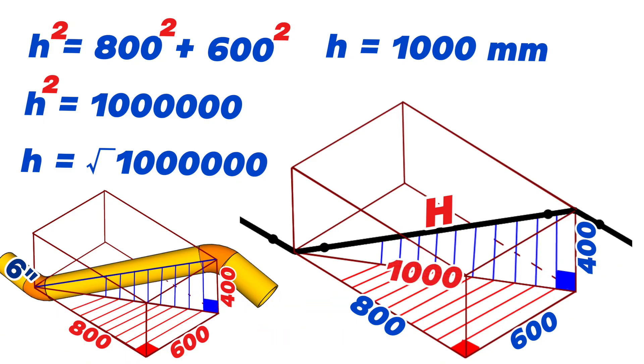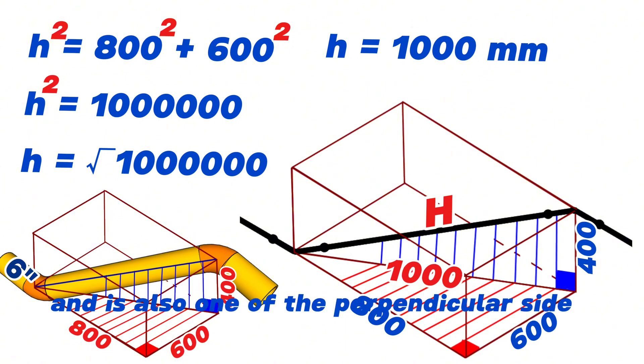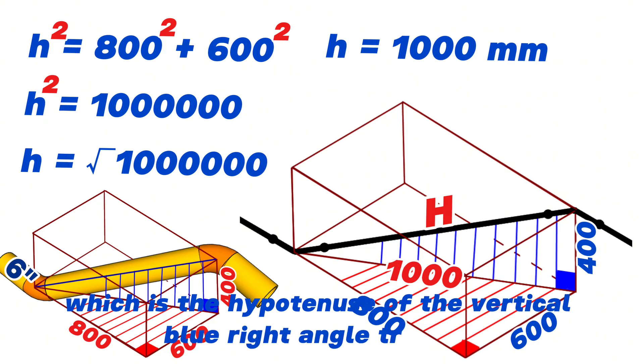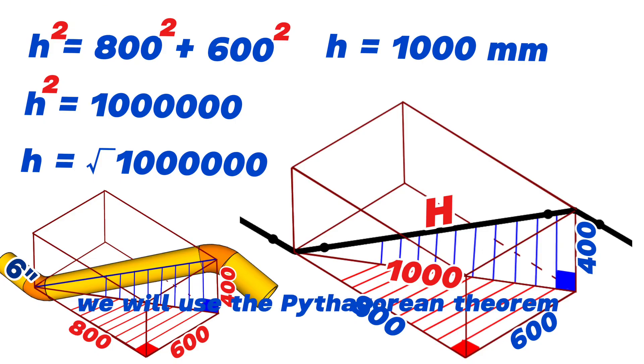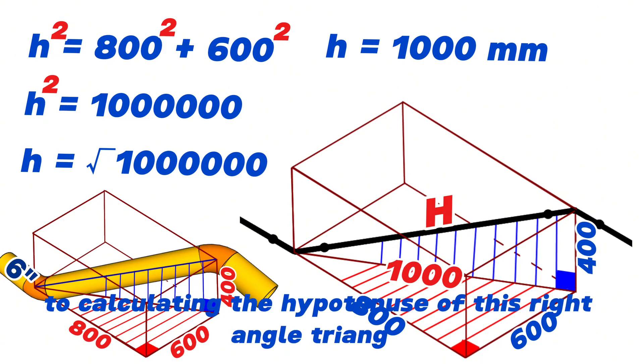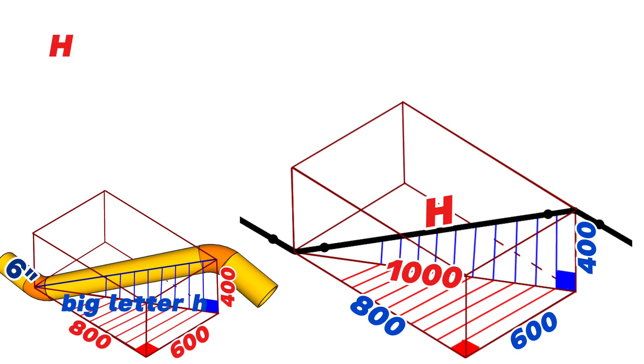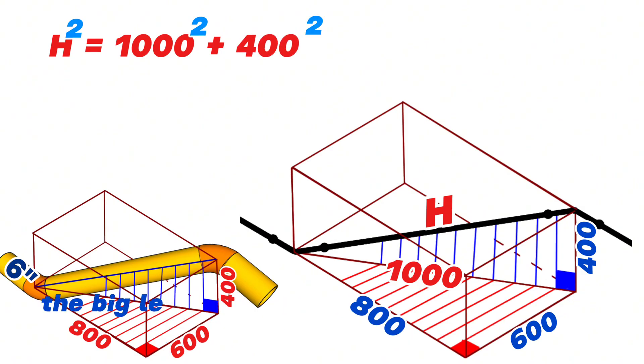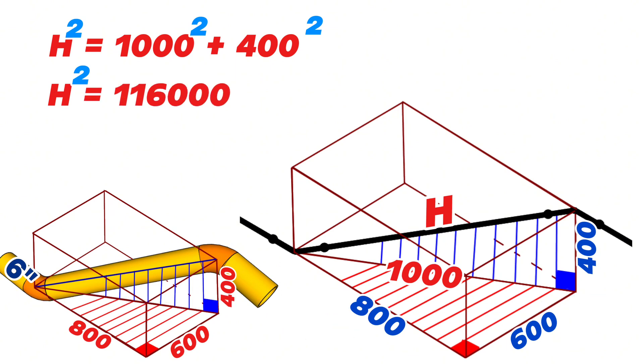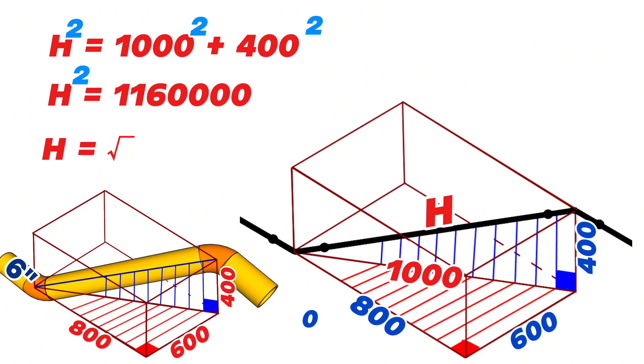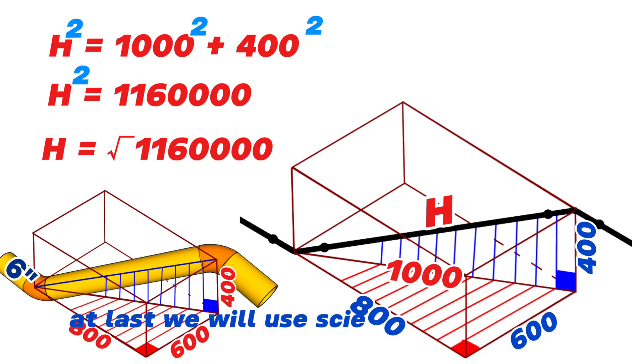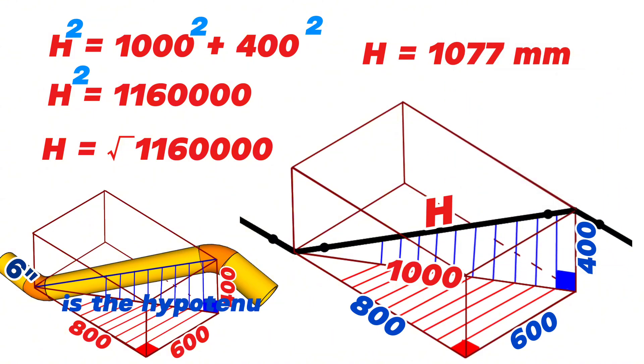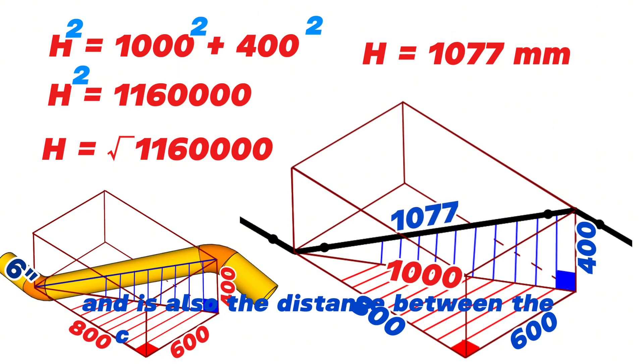1000mm is the hypotenuse of the horizontal red right-angle triangle, and is also one of the perpendicular sides of the vertical blue right-angle triangle. Now let's find big H, the hypotenuse of the vertical blue right-angle triangle. Using the Pythagorean theorem again: big H squared equals 1000 squared plus 400 squared, which gives big H squared equals 1,160,000. Therefore big H equals the square root of 1,160,000, which equals 1077mm — the distance between the centers of the butt-weld elbows.